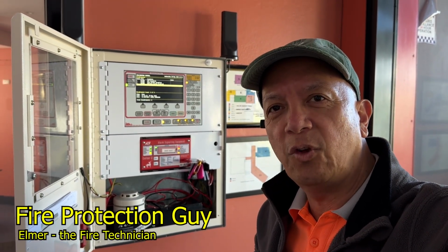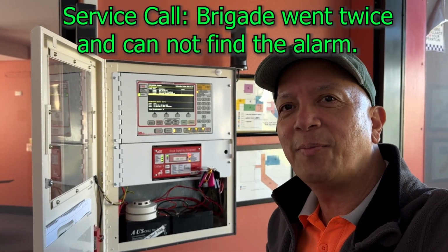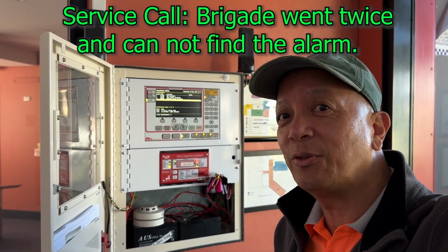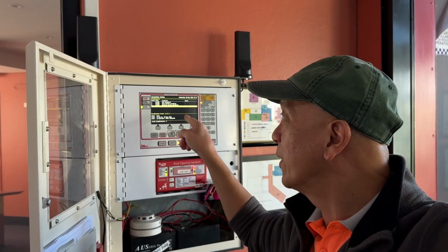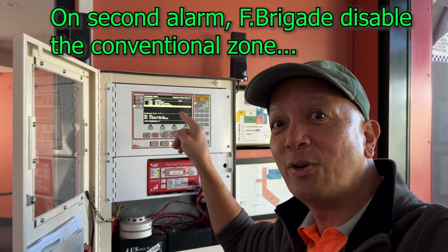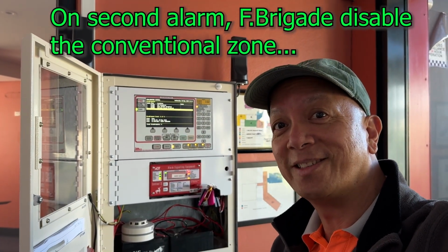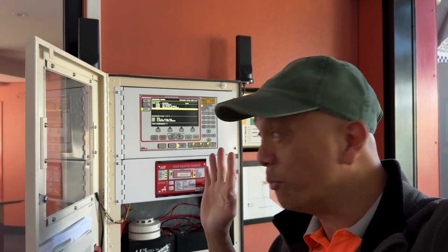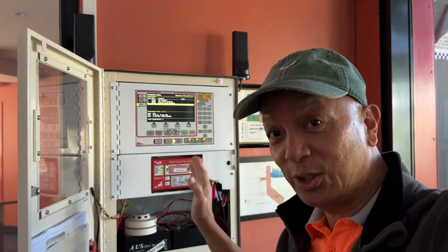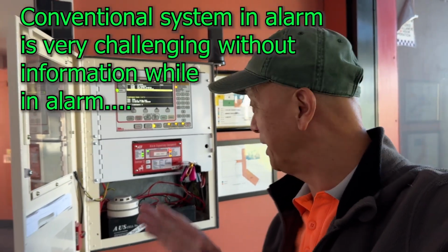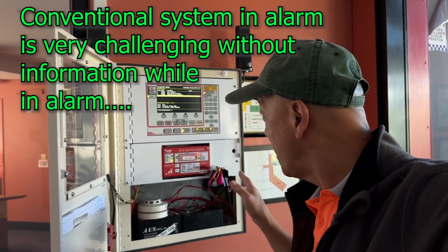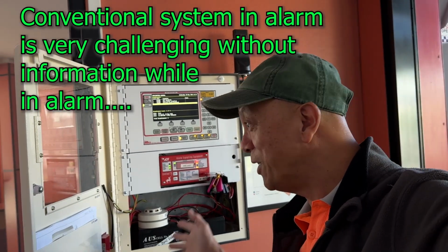What are you going to do if you have a call out and the fire brigade attended twice, and now you discovered that the fire brigade isolated that particular zone that went on alarm twice? Okay? First, this is a conventional system. It has history, but you don't know which particular detector was on alarm. So you look around and check if the fire brigade have left any notes. But in this particular fire alarm panel, I don't see any notes.